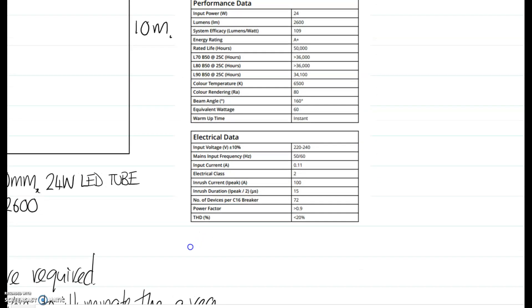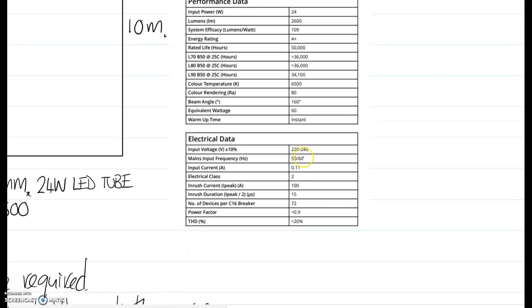If you look at the electrical data, you can see there is an inrush there, but basically ignoring the inrush for now, power factor is greater than 0.9, and it says there the number of devices per 16 amp circuit breaker is 72. So you can only put 72 fittings on a C16 breaker.